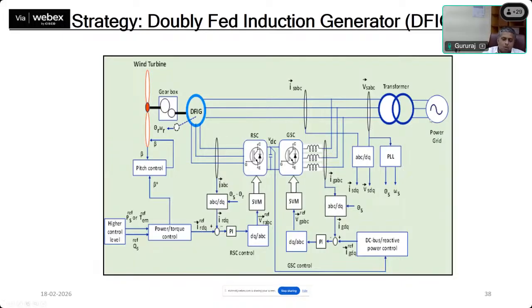So if there is a dip in the voltage, I just now declared that the fundamental principle is that flux is a state variable, and the flux cannot change by itself suddenly, but flux is dependent on the voltage. But the voltage has changed drastically, and flux will oppose the sudden change of the voltage, in its own language, by introducing a DC component of flux. That means a DC transient is introduced.